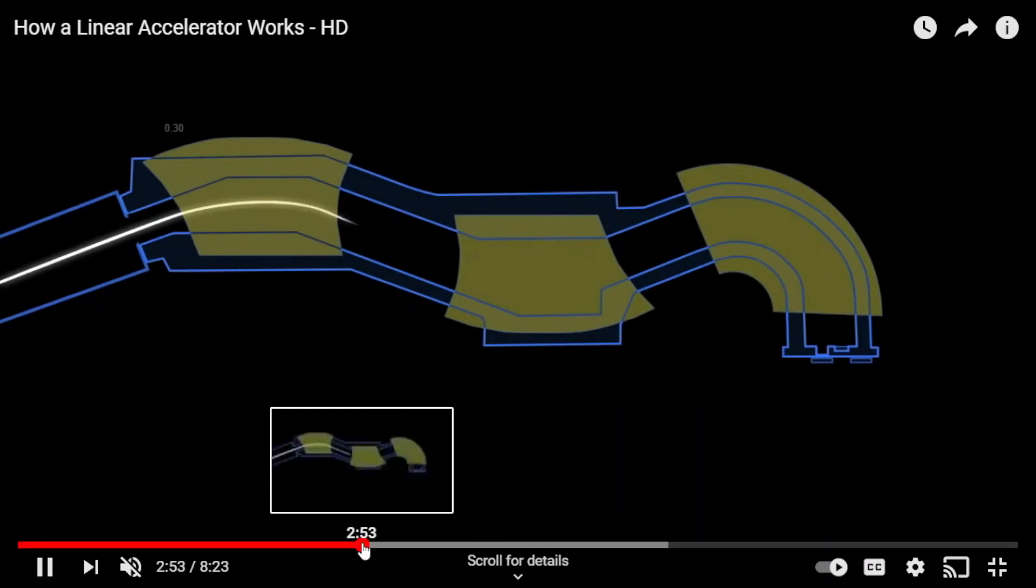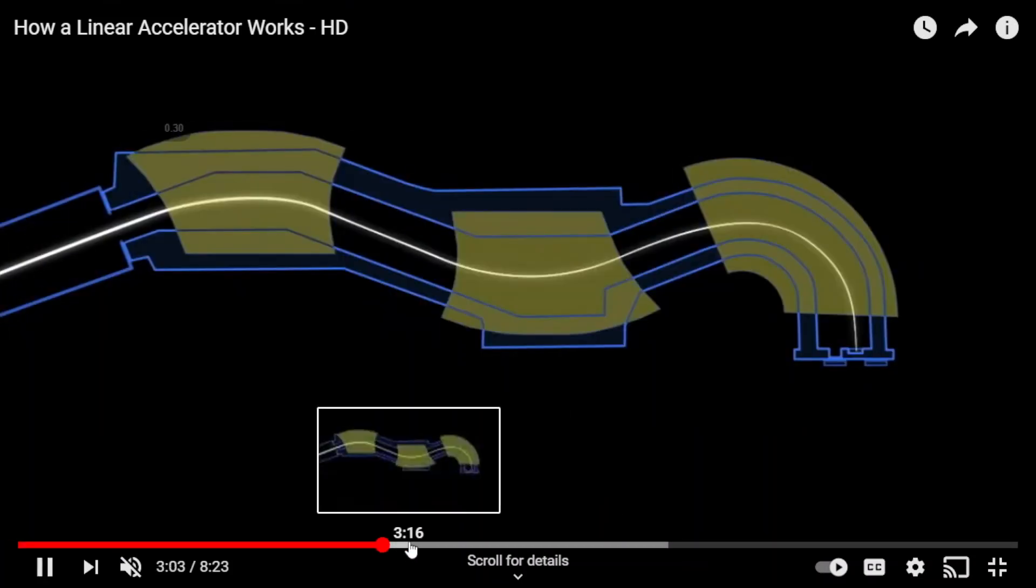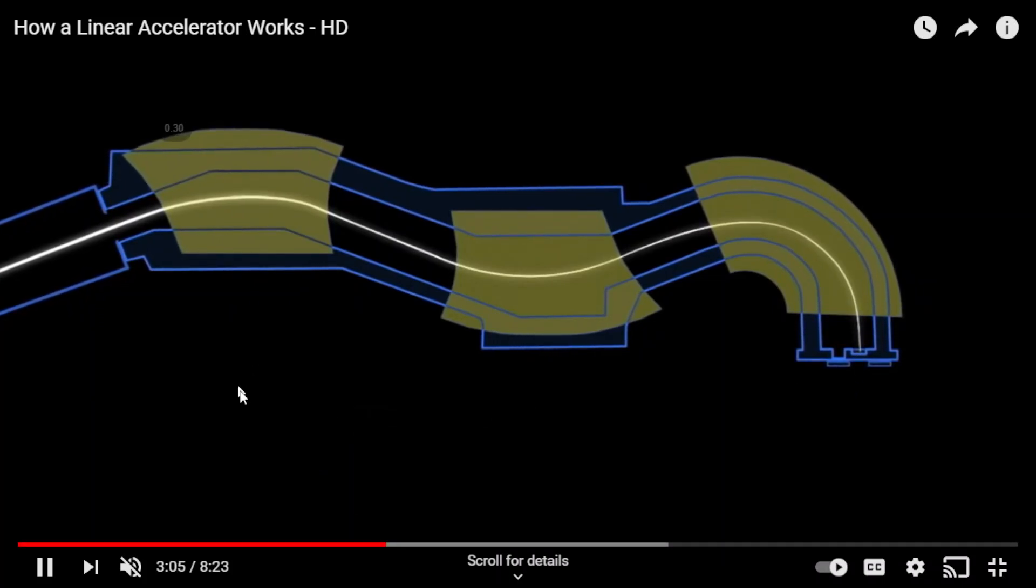As the electron leaves the accelerator tube, if the machine design has bending magnets, the electrons will go through them. The bending magnets will redirect the electron beam towards the target. Let me fast forward this, and you can see leaving the bending magnets here, and will hit the target after that.